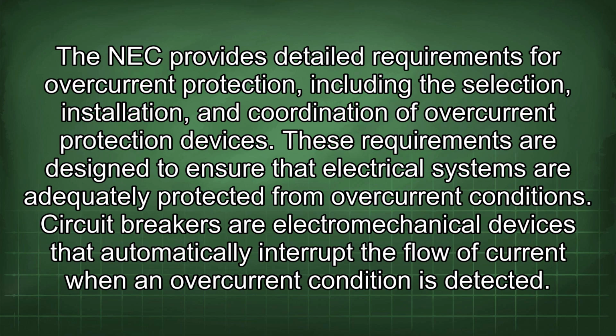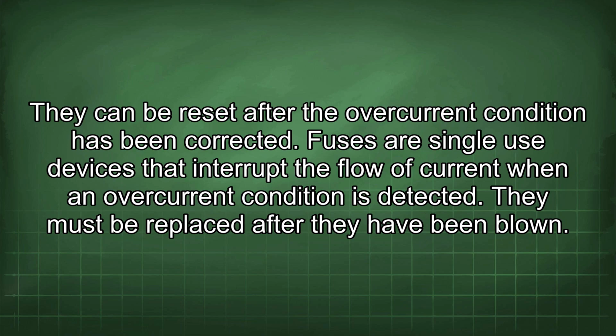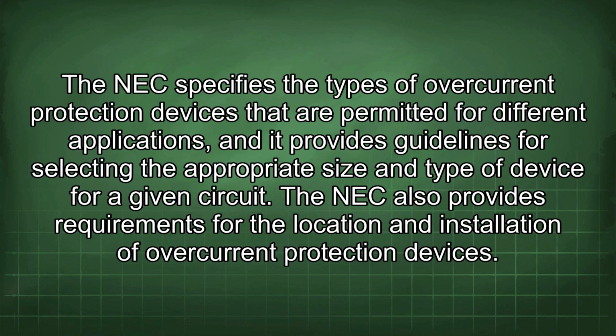Circuit breakers are electromechanical devices that automatically interrupt the flow of current when an overcurrent condition is detected. They can be reset after the overcurrent condition has been corrected. Fuses are single-use devices that interrupt the flow of current when an overcurrent condition is detected. They must be replaced after they have been blown. The NEC specifies the types of overcurrent protection devices that are permitted for different applications, and it provides guidelines for selecting the appropriate size and type of device for a given circuit.